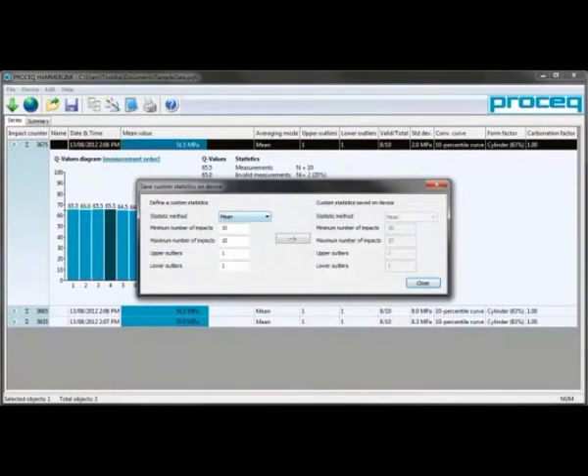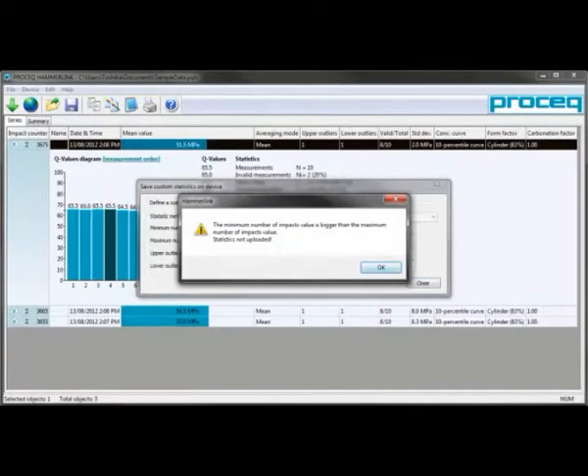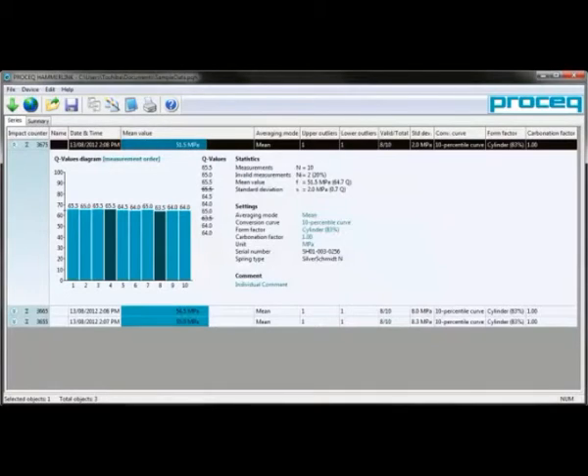We can also load custom statistics into our hammer. The 10 minimum and 10 maximum, with a drop of an upper outlier and a lower outlier, is a standard method, but you can use any method you choose. I'm going to set this back to 10, 10, 1, 1. We also have the option to select between mean and median.